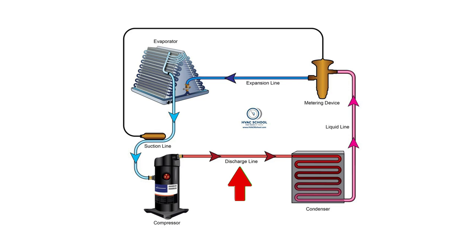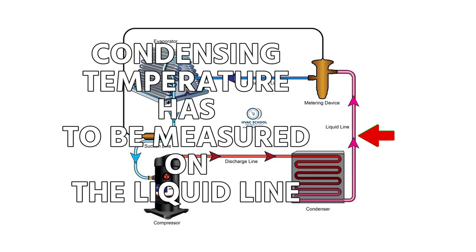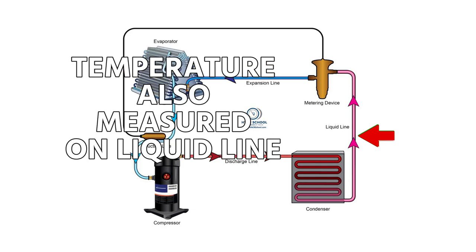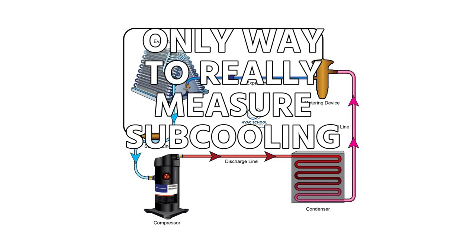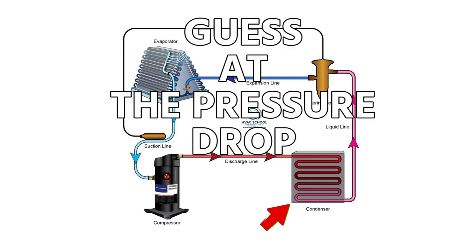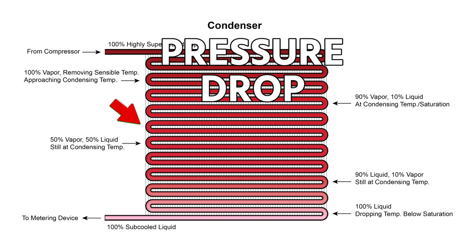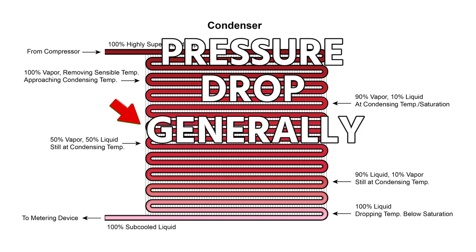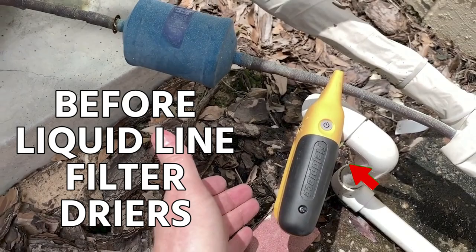A common mistake is somebody will measure the pressure and temperature on a discharge line and attempt to do subcooling — and that doesn't work. Subcooling has to be measured pressure-wise on the liquid line, and then the temperature also needs to be measured on the liquid line. In some cases, certain package units or rooftop units don't have a port on the liquid line, which makes it challenging. In those cases, the only way to really measure subcooling is to estimate the pressure drop across the condenser — I've been told that pressure drop is generally 10 to 15 psi. But there is no way to accurately measure subcooling unless you can take a pressure on that liquid line, and the ideal place is right after the condenser and before any liquid line filter dryers.